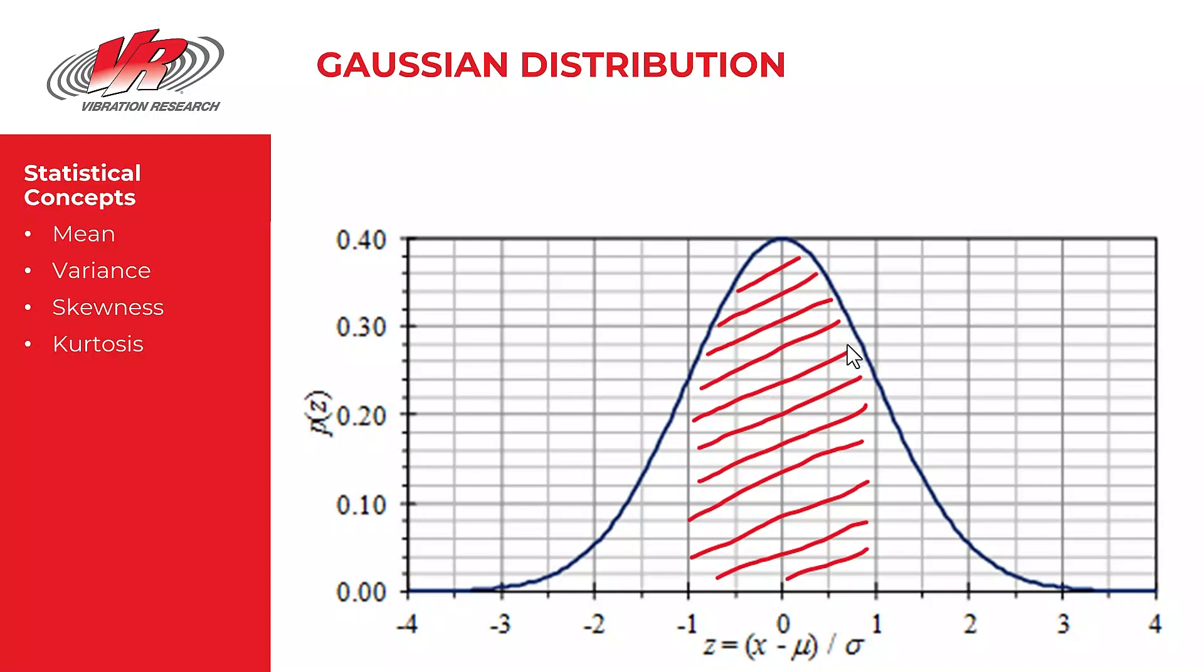And a truly Gaussian distributed set of data will have 68.3 percent of its points, or in our case of vibration data, 68.3 percent of the vibration peaks are going to land within one standard deviation of the mean.